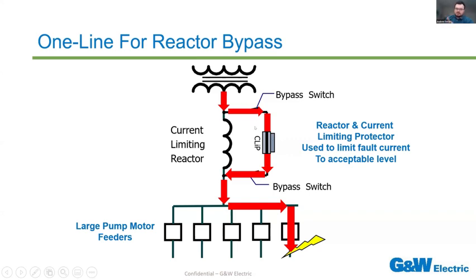And under normal operation with a clip and reactor in parallel, what's going to happen is that current's going to choose the path of least resistance, which is through the clip, and avoid incurring any kind of power loss or power quality issues from the added impedance of that reactor. However, if the clip were to trigger and open, then all of that fault current would go through that current limiting reactor instead, which would ensure that there's no downtime. However, in that scenario, they would start incurring those power efficiency and power quality issues. So it's an interesting solution called the reactor bypass that I've seen a couple times in the past.